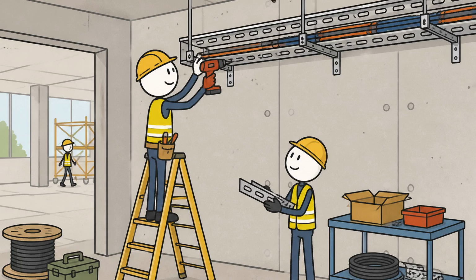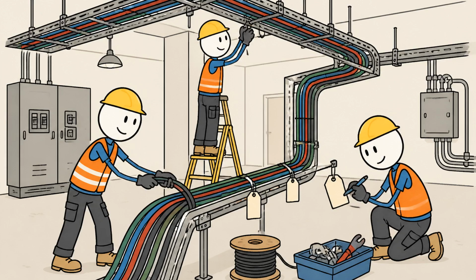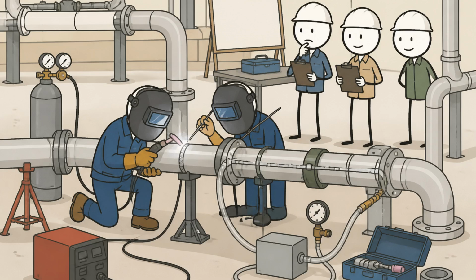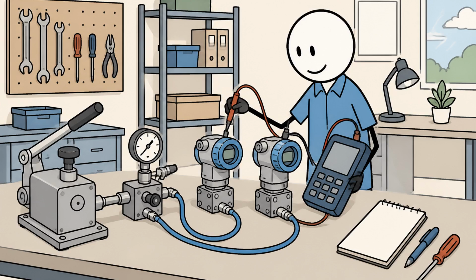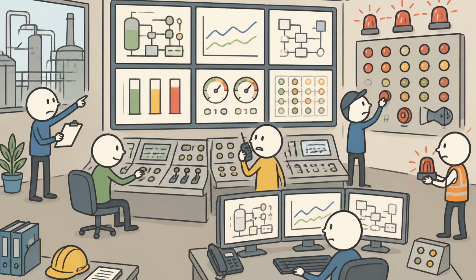Electrical fit-out is painstaking; each circuit must be tested, tagged, and documented. Piping welds are radiographed, with quality records tracing every weld, filler, and welder. Instruments are calibrated, loop-checked, and proven through end-to-end function tests. Control logic is exercised in dry runs before energizing live systems safely.